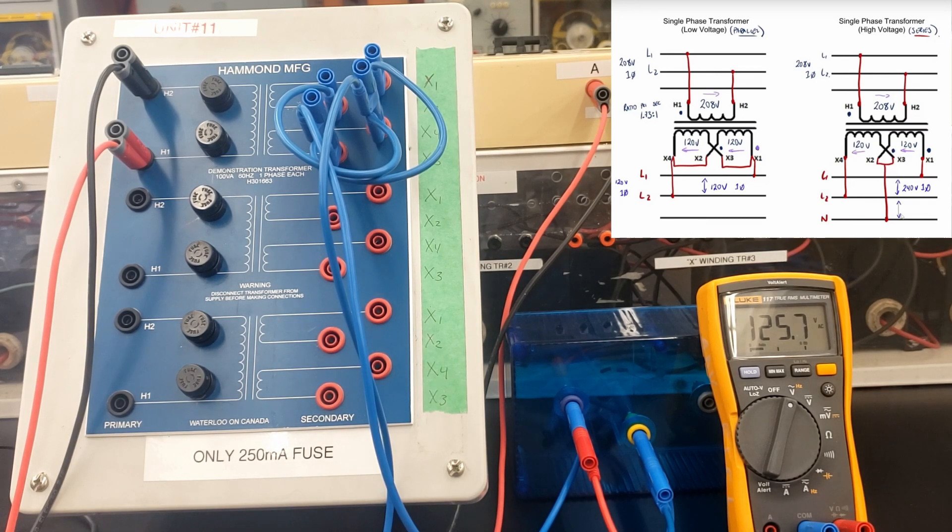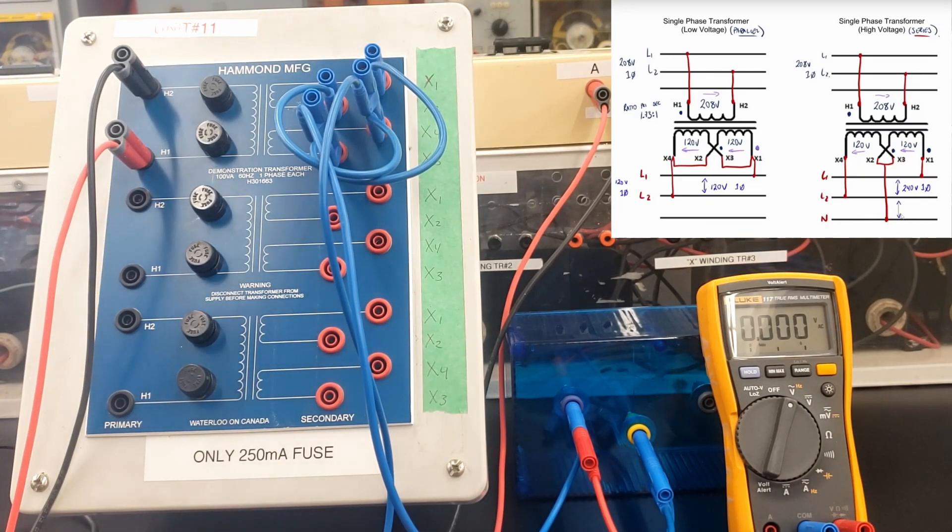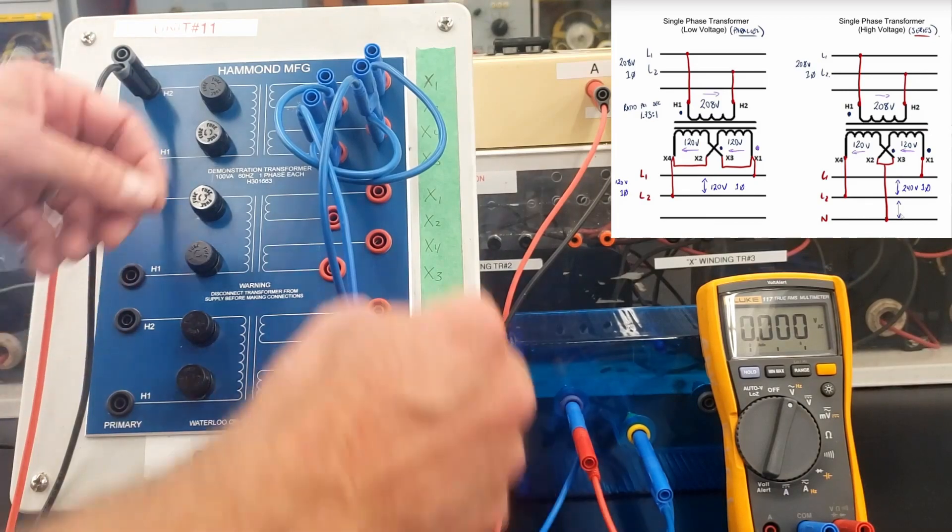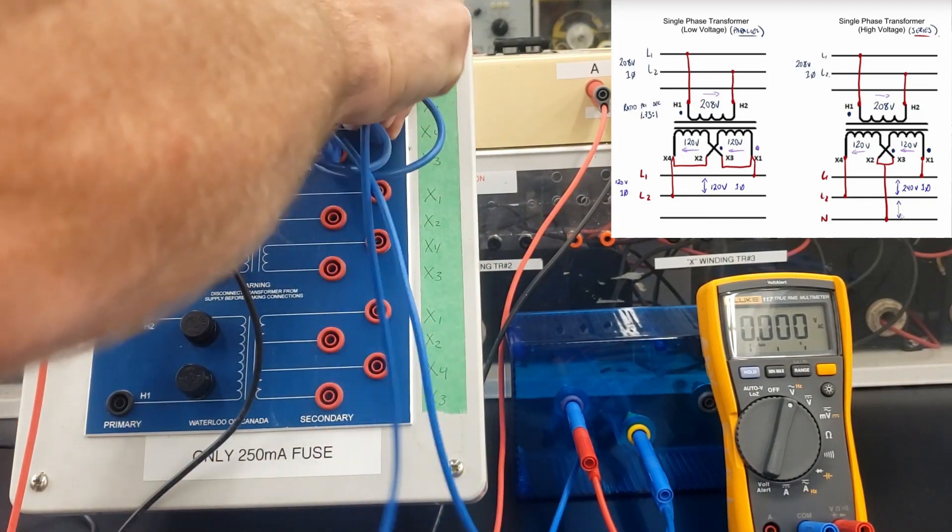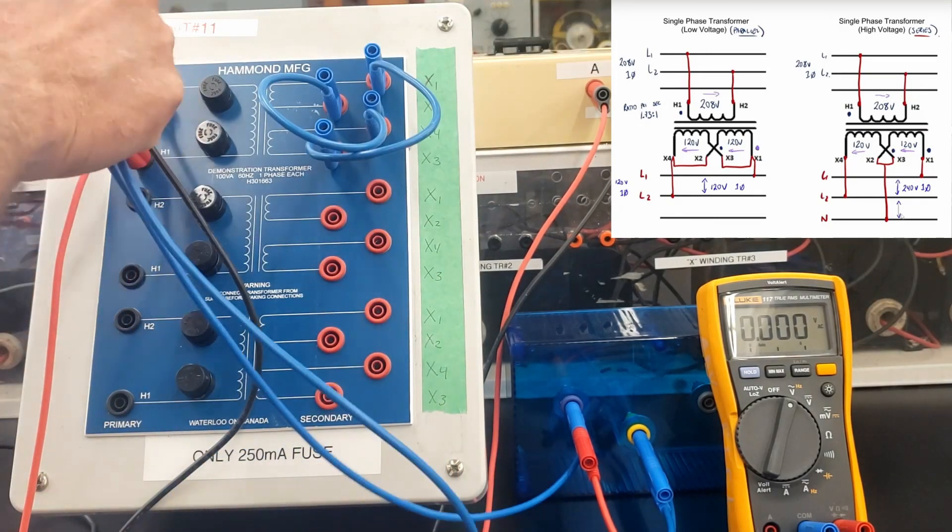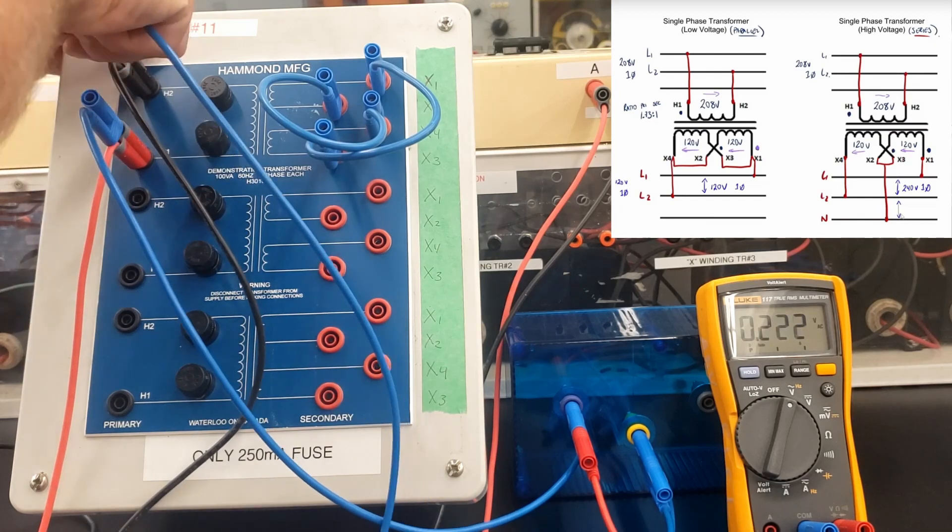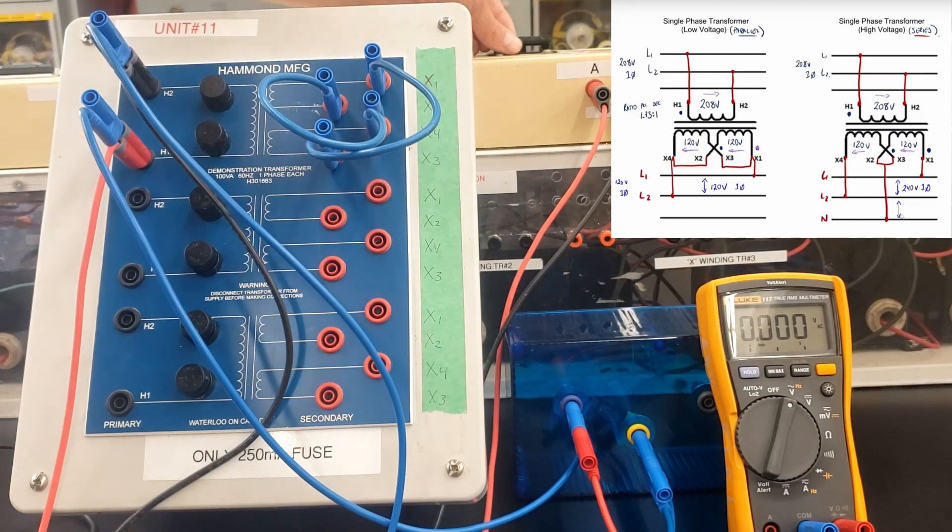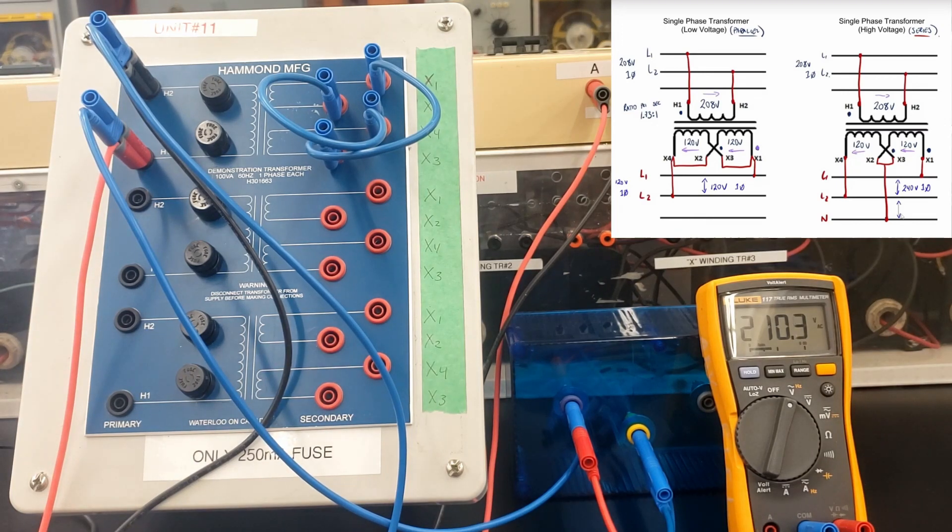On these transformers, there are two secondary windings. And they have identical voltages of 120. In this case, 125, 126 volts. Remember that these voltages are higher at the moment because we don't have a physical load that is connected to the secondary of the transformer. If we hooked up a load to the secondary here, then we would see the voltage drop to 120 volts. Primary voltage was 208.